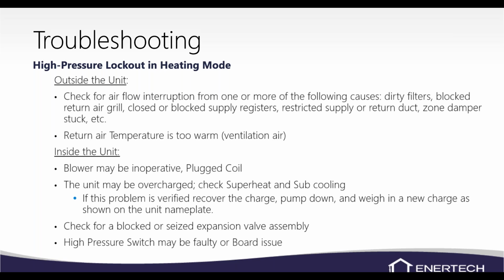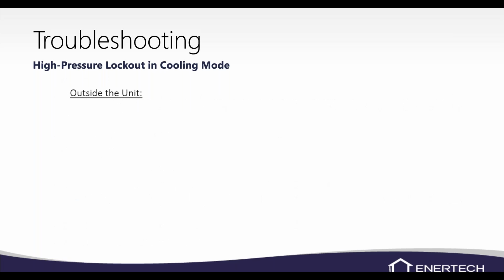So if the switch is good, then jumper it out at the unit. If the lockout board still locks out when you've jumpered out the high pressure switch, then we know we've got a board problem, so the board would have to be replaced. High pressure lockout in cooling mode. So now we're going to be looking at our source side.